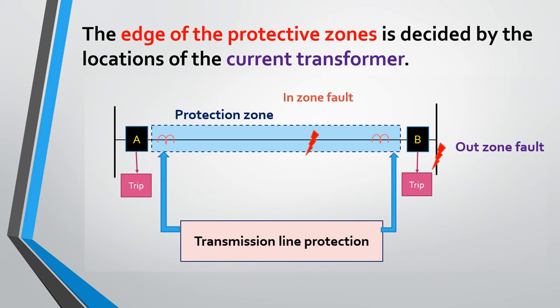In this diagram, CT1 and CT2 decide the protection zone for this particular transmission line. If a fault occurs between these two CTs, it will be sensed by the relay coils, which will trip circuit breakers A and B. If a fault occurs outside the zone or on the bus bar, these CTs will not sense it and will not trip the circuit breakers, which may result in complete shutdown of the power system. That is why protection zones are very important and are decided by current transformers.